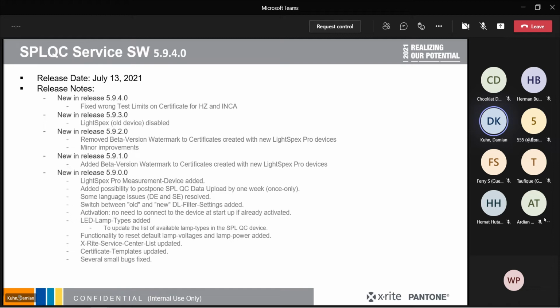If you are unsure whether the instrument you are going to test is equipped with one or the other, I would recommend that if the device is older than about 2018, you can assume it has the old filters. If it's a newer instrument, produced in 2019 or newer, then most likely the new filters are installed. Of course, somebody may have replaced the old ones with the new ones, but if you're unsure, you can calibrate with one or the other setting. If you test with the old filter setting but have new filters installed, it will fail daylight with too much light, so your values will be above the limits. In that case, you would simply recalibrate daylight with the other daylight filter setting. So that's one of the changes we made to the software.